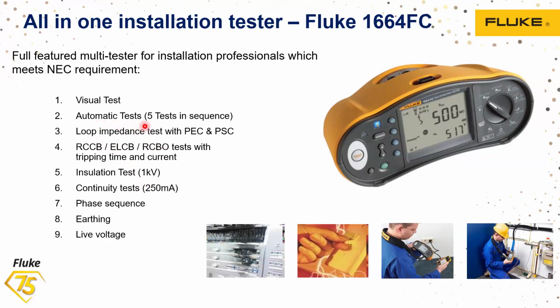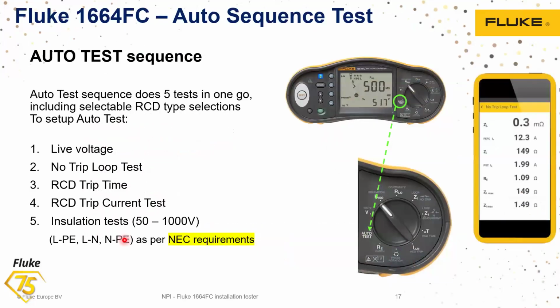This product has an automatic test sequence. So I'll explain what the automatic test can do. Loop impedance test, and it will automatically calculate the prospective fault current and short circuit current. RCD testing, insulation test, continuity test with 250 milliampere current injection, phase sequence, earth loop test, then live voltage detection. These auto sequences will definitely help you, because this will complete 5 tests in one go.